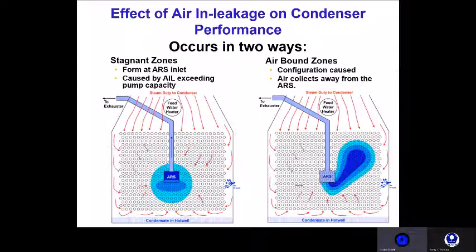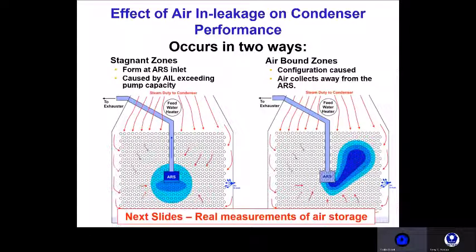One of the services we have developed is the direct measurement of air storage. We install hundreds of temperature sensors inside the condenser to measure the real-time heat transfer of tube bundles. On the next couple of slides, I'll show you real measurements of these different types of air storage.